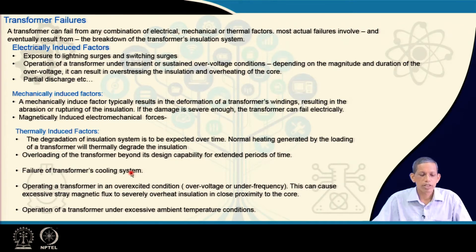Now, there are different transformer failures. It may be a combination of electrical, mechanical and thermal factors, and finally it culminates in insulation failure and subsequent damage to the transformer, even though it may start due to some mechanical or thermal factors. We have divided the factors for transformer failures here into three categories: electrically induced, mechanically induced and thermally induced.